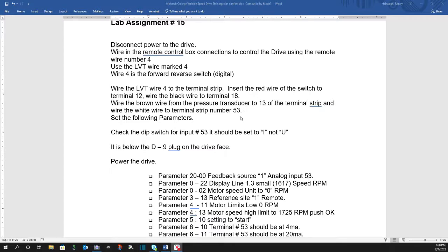And now we're going to wire in the transducer. And you can see that the brown wire from that M12 wire is going to go across 13. That's my power source. And the white wire is going to go to terminal number 53, which will be the variable input from 4 to 20 milliamps. All right. Another thing that's not so obvious to see is I've got to convert the accepted input signal from voltage, which is U, to I, which is current, milliamps. So you can see that right here.